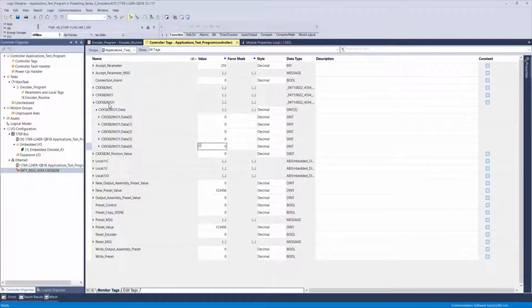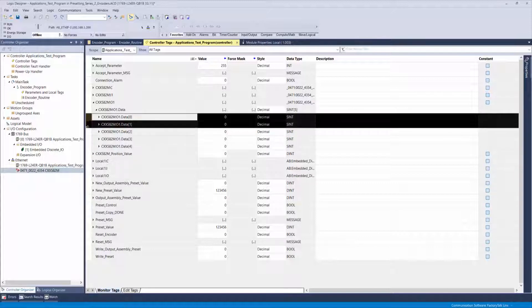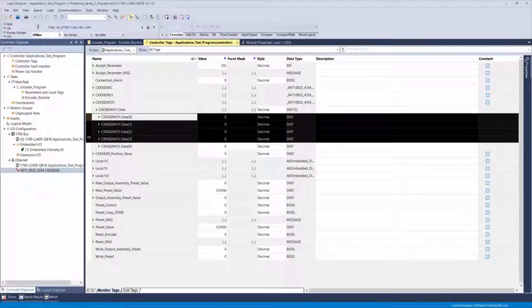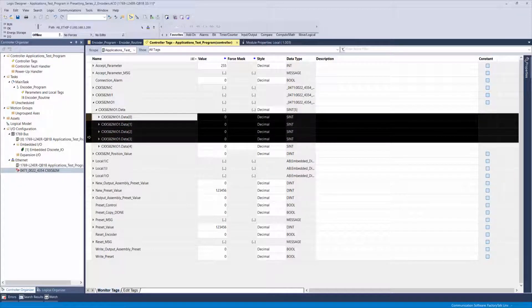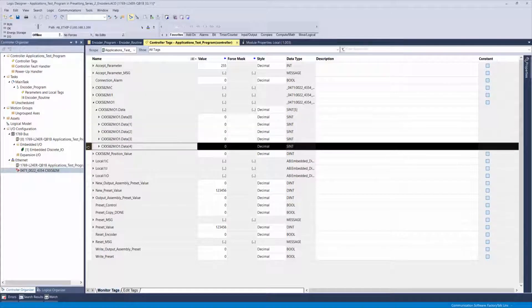The output assembly is denoted by a colon 01 after the device name. The first four bytes of data are used to define the preset value that you want to write to the device, and the fifth byte is used to perform that preset.